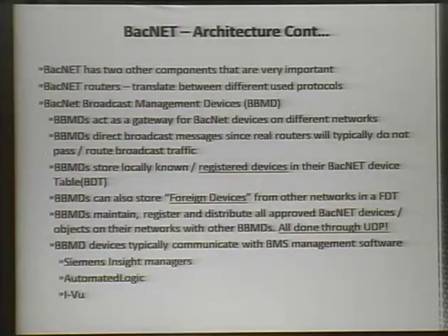But the device in the center, this BBMD device, is what kind of acts as the brain. It allows all these disparate types of network topologies, such as Modbus or master-slave token passing or serial connections, to communicate over a standard TCP/IP type of connection that comes out of the backside of this. So these become kind of that central routing or gateway point. I said 2 components that I really want to focus in on just a little bit. I talked about the BacNet gateway device, or these routers or broadcasting equipment. They store 2 things that are kind of important for us.